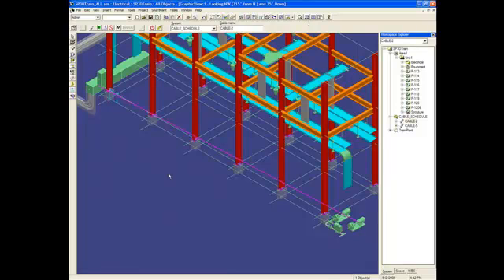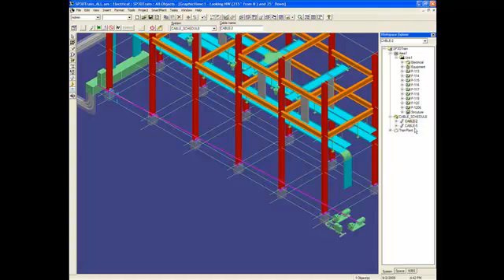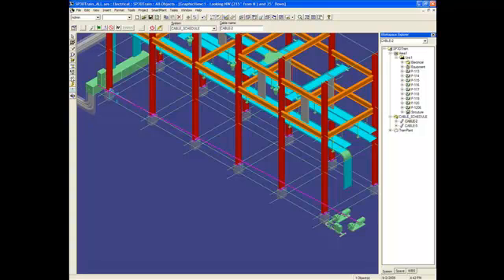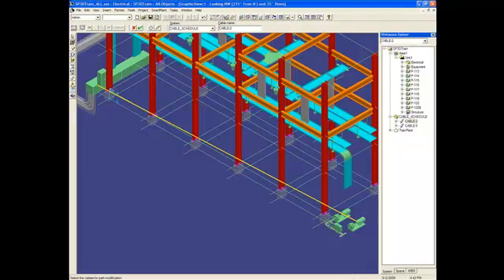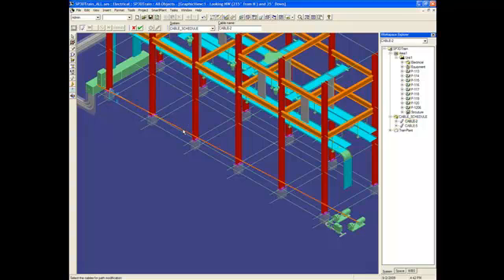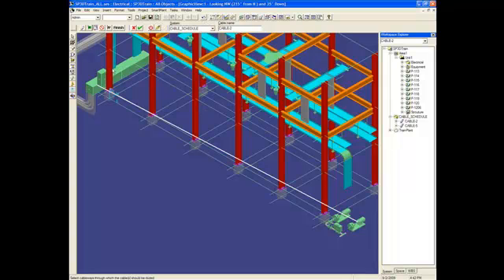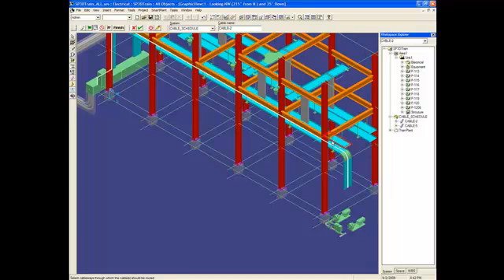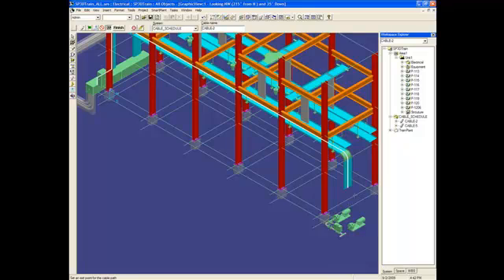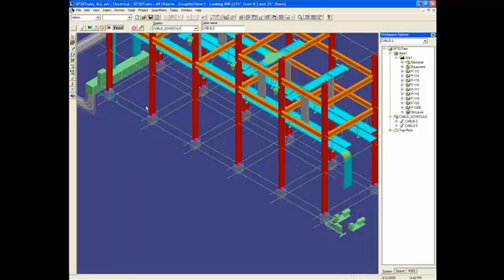So what I'm going to do now is, for each of these cables, I will select to edit the cable path. So I'm going to select this cable, I'll accept. Now it's asking me for the entry point of the cable. I will select this, and you see it goes on the tray. I'll accept that. It asks me for the exit point for the cable, and it routes from the exit point to the pump. I'll finish, that cable is done.